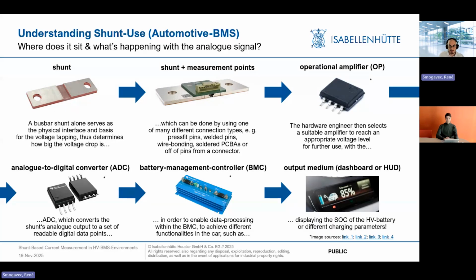Subsequent to that, you usually need to amplify the signal you're getting from the shunt, meaning the voltage drop, which usually ranges between 10 to 500 millivolts, meaning it's too low for direct processing of this differential signal. So usually the signal is getting filtered and converted through an ADC, and before that going through an operational amplifier to be amplified at 1 volt up to 5 volts or whichever is needed.